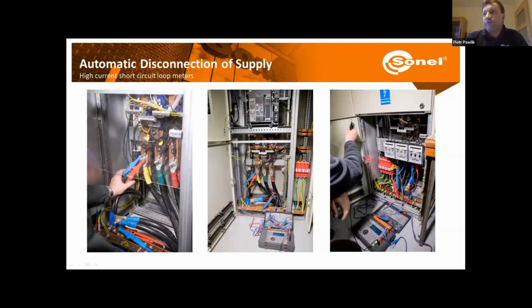Okay, now what in case we want to measure a fault loop directly on a transformer? Well, for this reason, we're going to need to use more precise and more powerful meters, because then the whole distance of the loop will be very short, because all the wires that we need to measure will be very short. And for this reason, we have our high models of fault loop meters, so the MZC series in Sonel, and that will be MZC 310, 320, or 330. So here you can see the model 310.